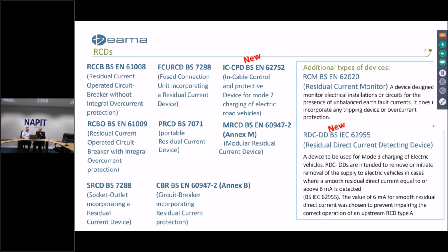RDC-DD on the right-hand side, this is not strictly a residual current device, but it's a detecting device. It's not the same as an RCD per se. It is to detect 6 milliamp DC and open if it detects that level of current. Again, for use in EV charging, covered by BS IEC 62955. And the final one, just to mention, on the top right, is the residual current monitor.